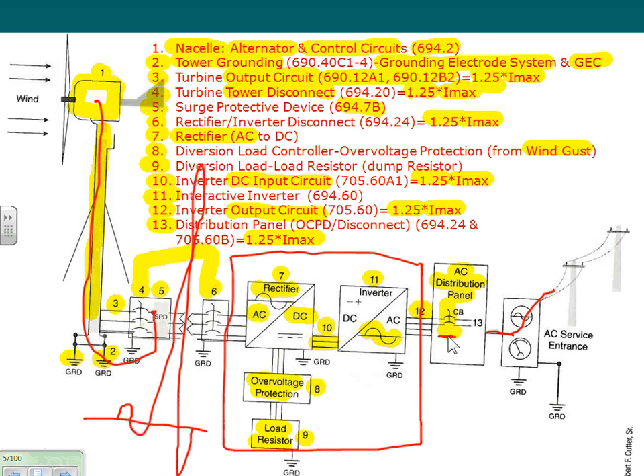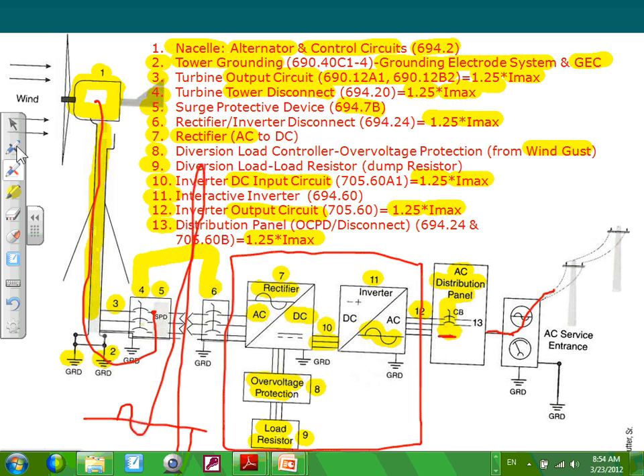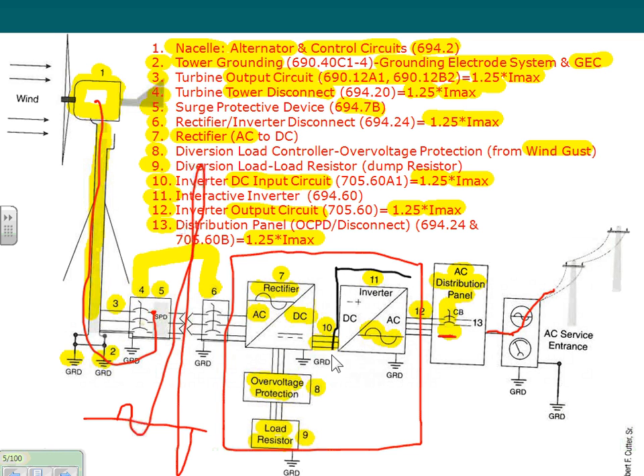Yeah, very good point. Now you have an inverter. Let me just grab my black marker here. This inverter, I think I forgot to say one very important thing about it. It has to be a listed interactive inverter. Part of the listing is that it has to have two major things. You have to have arc fault protection on solar. And they have to be able to sense the loss of power.